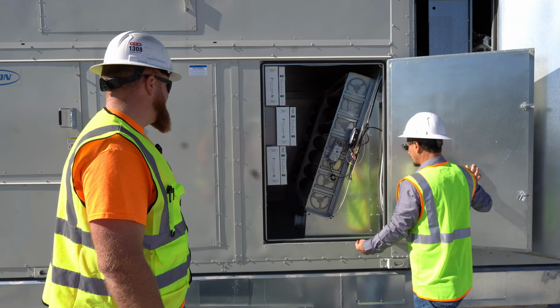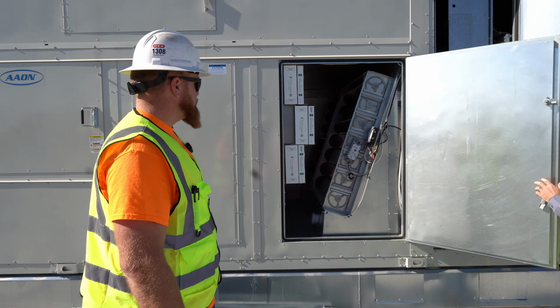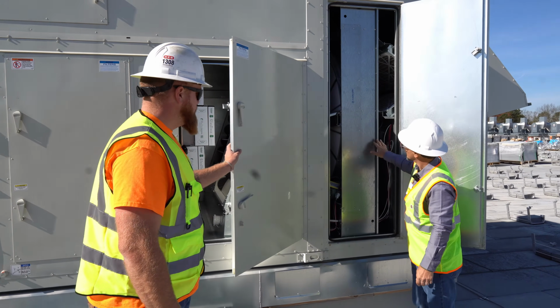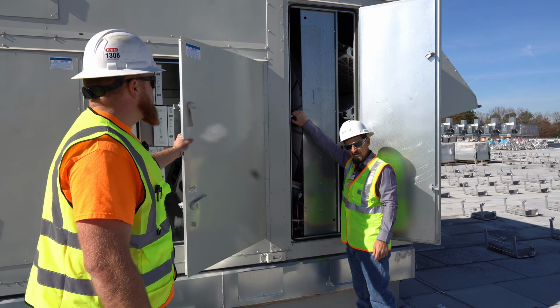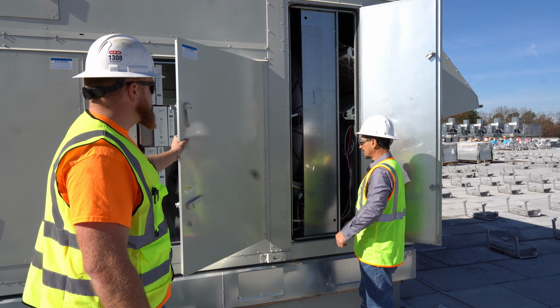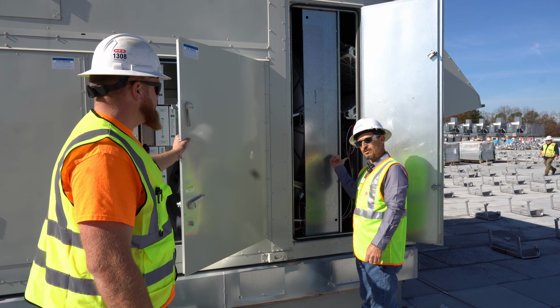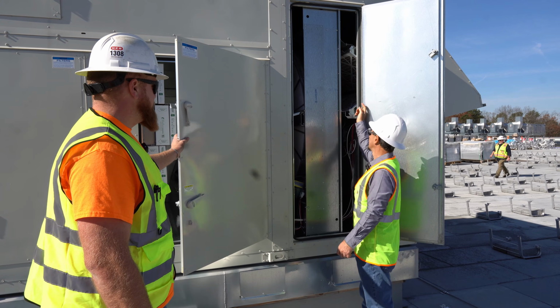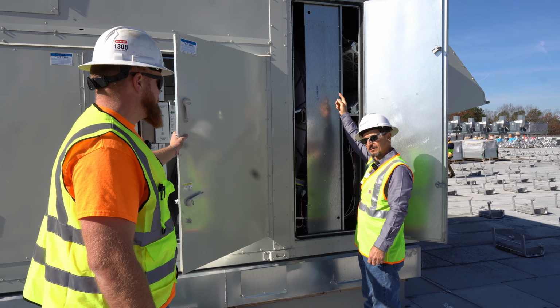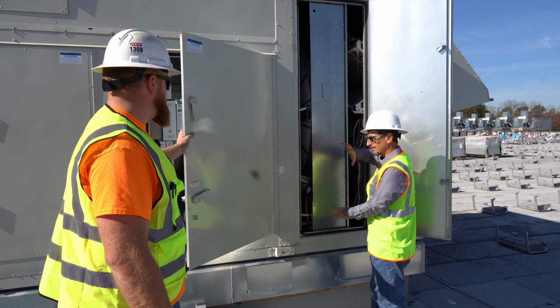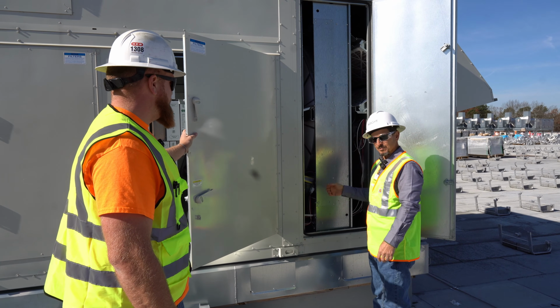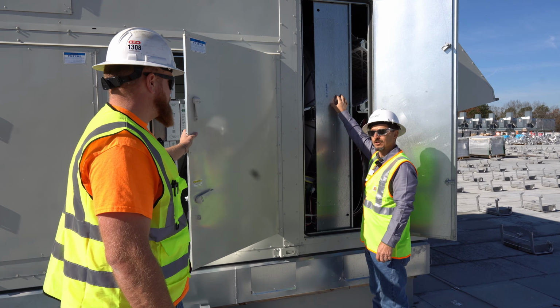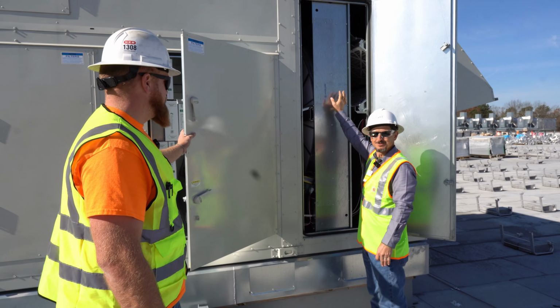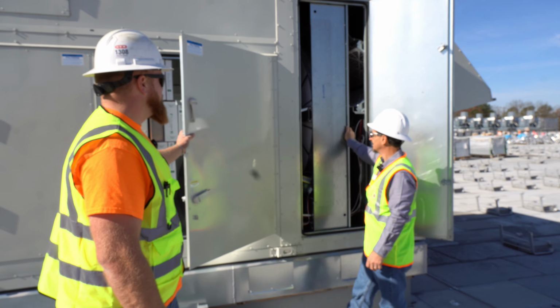So exhaust return air is coming up through here, going through the wheel, which is separated by this plate here. And it's exhausting out. So this is relatively cool and dry on a summer day compared to this very hot and very wet air. The energy recovery wheel takes the energy and moves it around. It pre-cools and lowers the humidity -- I hate to use the word dehumidifies, but it lowers the humidity content of the outside air.